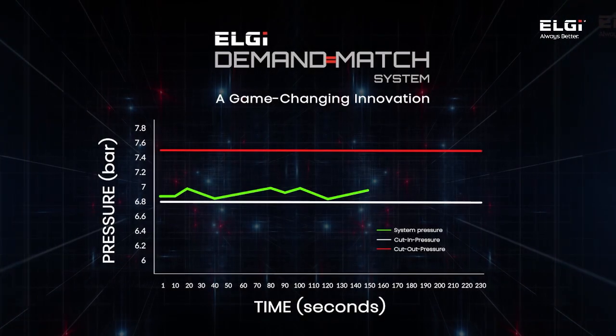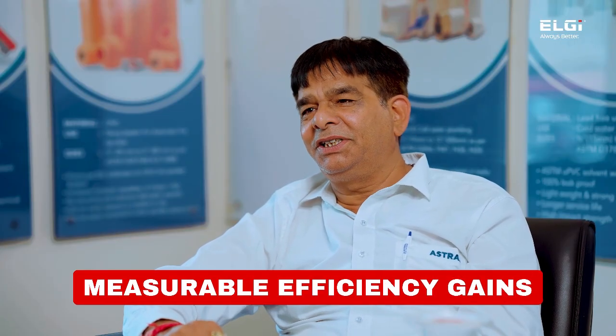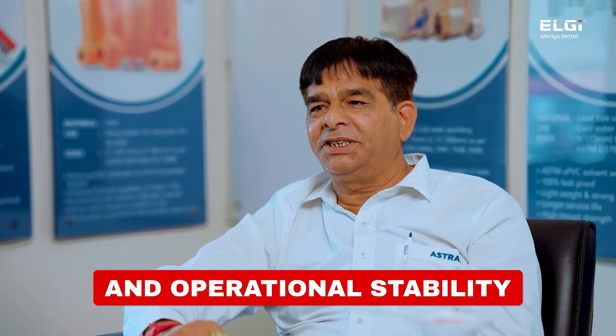The compressor with the demand-match system is operating more stably than the other units. With the demand-match system, there are no cut-in cycles. This stable operation boosts equipment life and ensures more consistent performance throughout our production line. ELGi's partnership has been instrumental in helping us achieve measurable efficiency gains and operational stability.